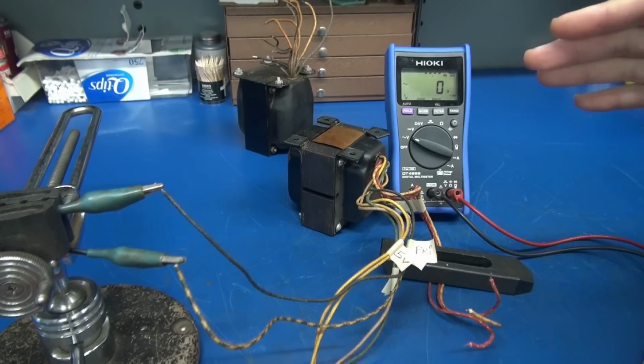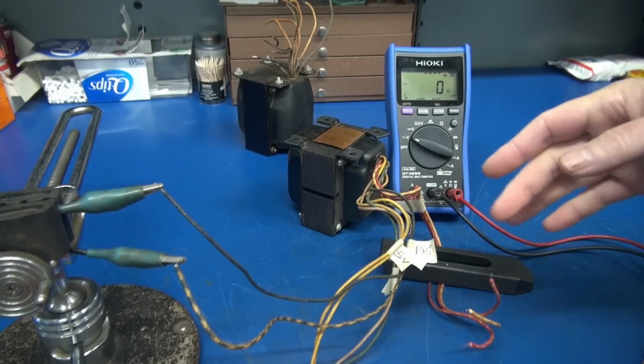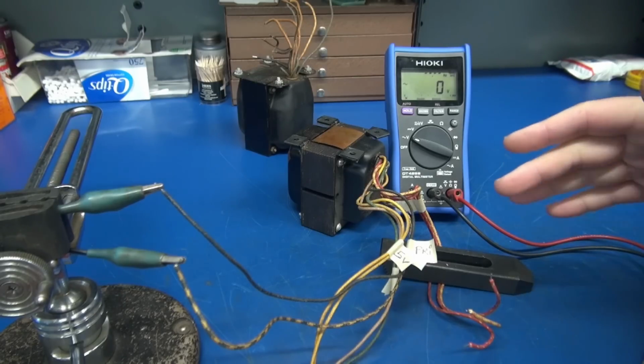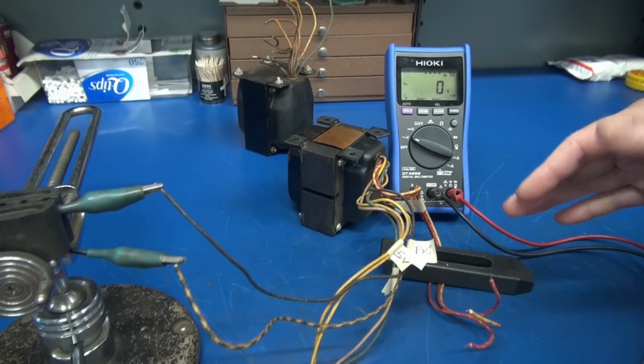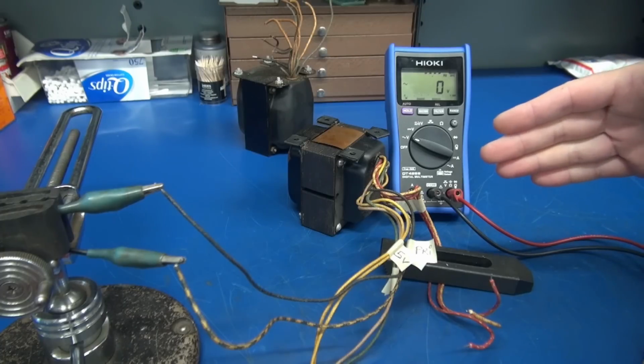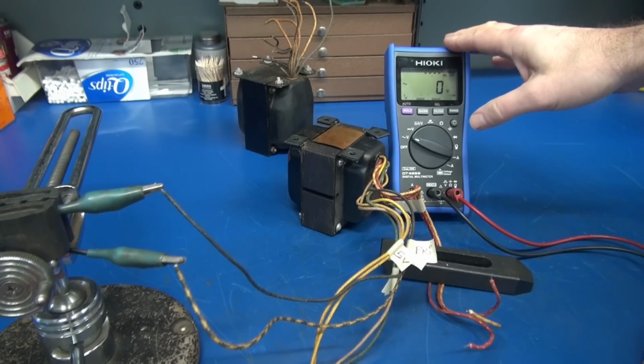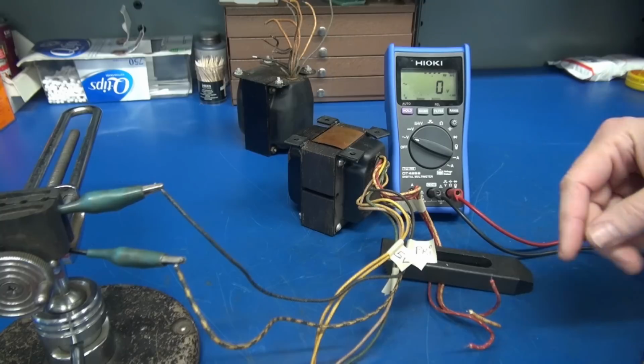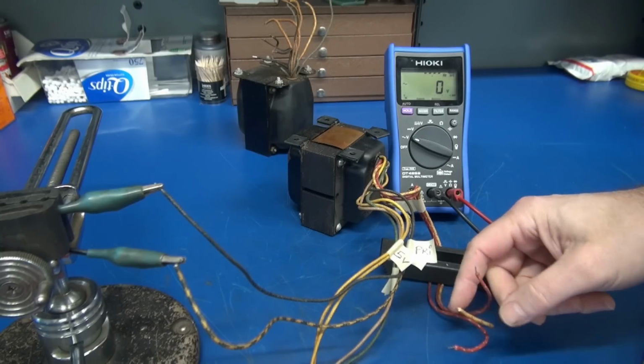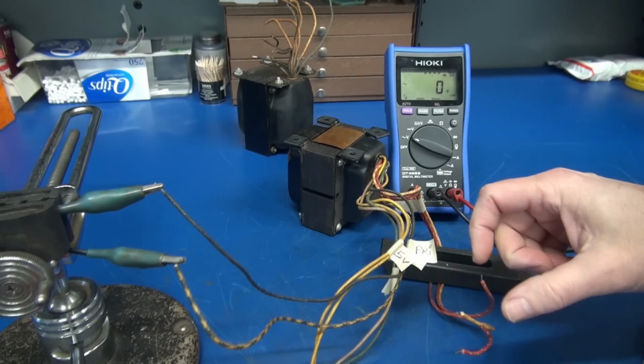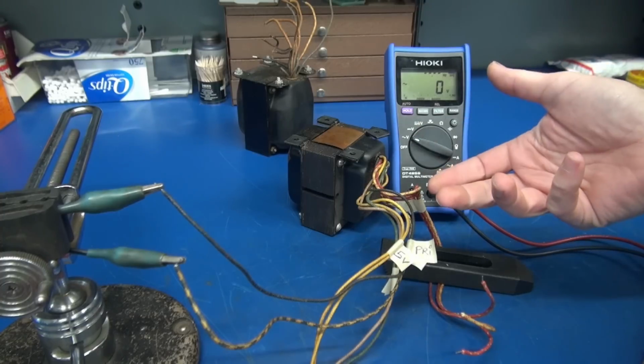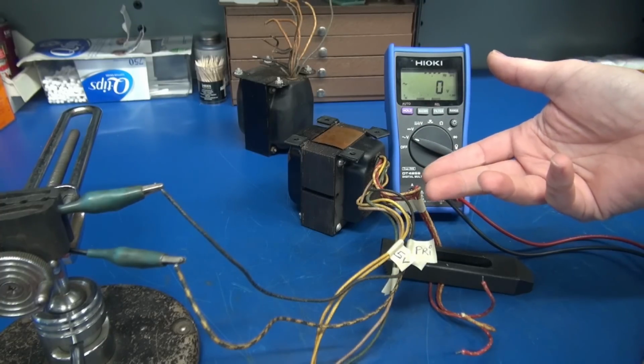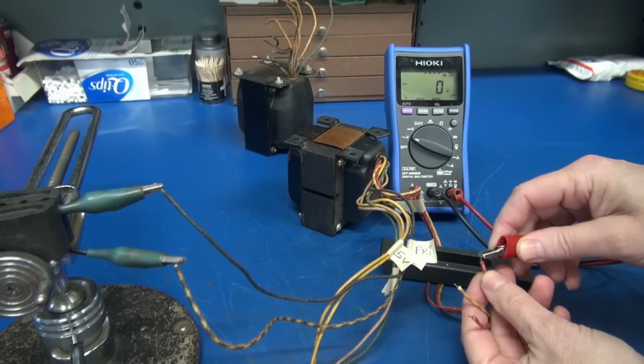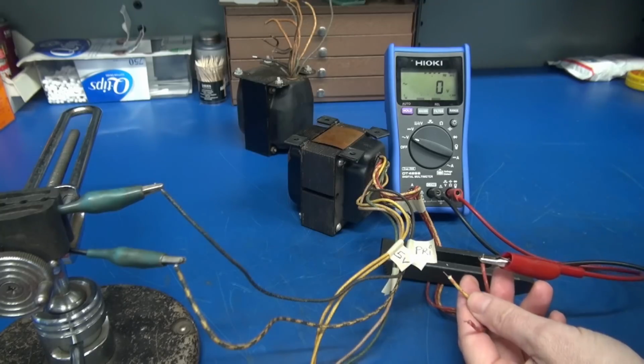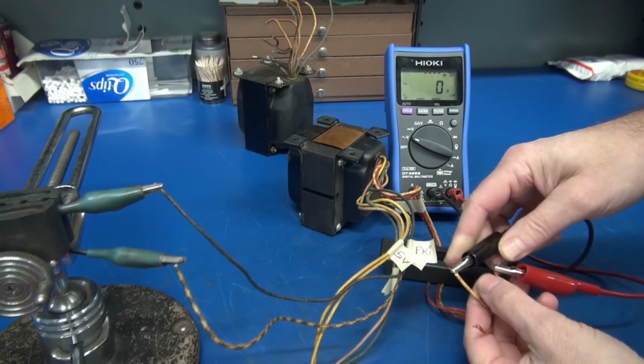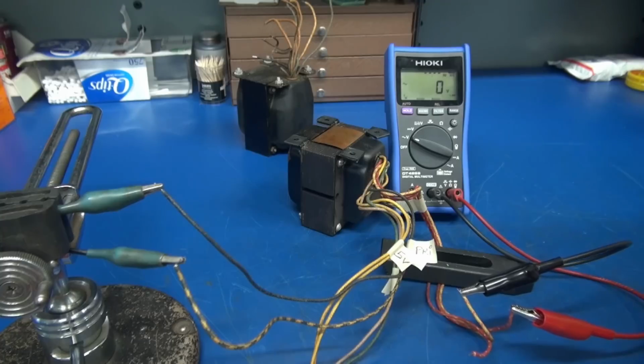The other issue you'll run into measuring this high voltage is your meter itself. A lot of lower end multimeters have a limit of 600 volts AC input. This Hioki can handle 1,000. So let's say this was a 1,000 volt center tap transformer and you hooked the two reds to a meter that could only handle 600 — you're going to damage it. That's why you should always go from red to the center tap, and whatever that reading is, you just double it.